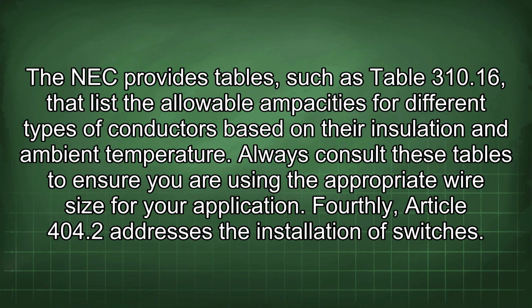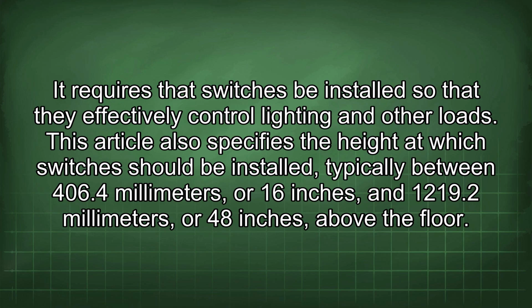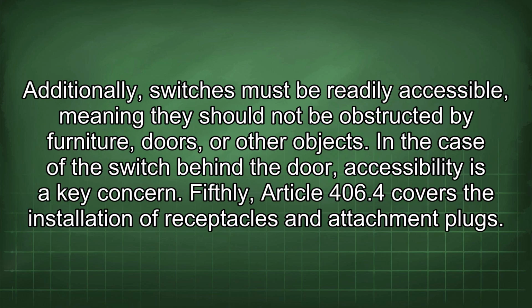Fourthly, Article 404.2 addresses the installation of switches. It requires that switches be installed so that they effectively control lighting and other loads. This article also specifies the height at which switches should be installed, typically between 406.4 mm or 16 inches and 1219.2 mm or 48 inches above the floor. Additionally, switches must be readily accessible, meaning they should not be obstructed by furniture, doors, or other objects. In the case of the switch behind the door, accessibility is a key concern.